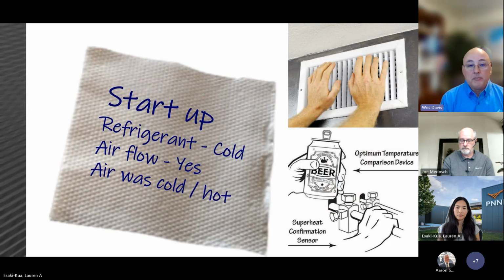Last but not least, commissioning. I've got nothing against writing something on a napkin if that's all you've got. It's not the best way to do it, but if you're at least documenting the correct information, it's a step in the right direction. However, refrigerant line, cold, airflow, yes. And then for extra credit, it was cold in the air conditioning mode and warm in the heating mode.